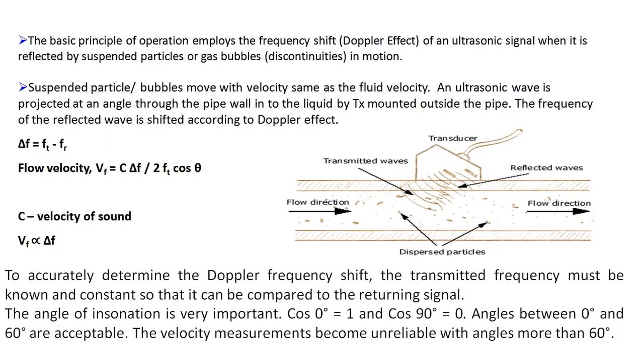The basic operating principle employs the frequency shift of the Doppler effect of the ultrasonic signal when it is reflected by suspended particles or gas bubbles present in the liquid. One disadvantage of the Doppler effect type is that there must be some foreign particles or gas bubbles present for proper operation of this flow meter.